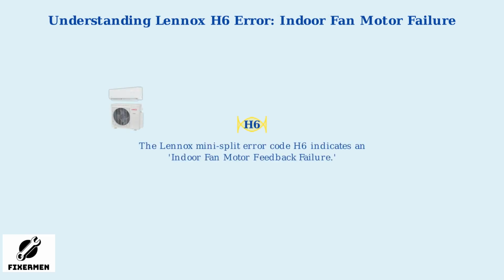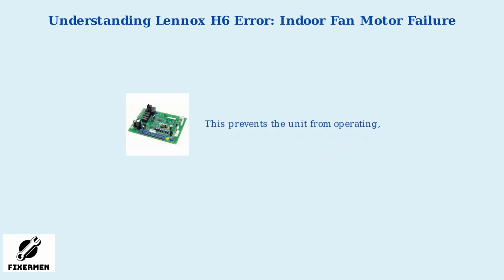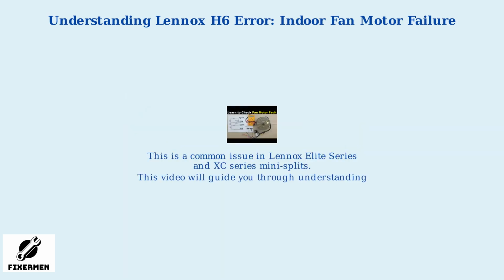The Lennox mini split error code H6 indicates an indoor fan motor feedback failure. This means the system's control board isn't receiving the correct signal from the indoor fan motor. This prevents the unit from operating, usually with the fan not spinning or the system shutting down completely. This is a common issue in Lennox Elite Series and XC Series mini splits. This video will guide you through understanding and addressing this error.